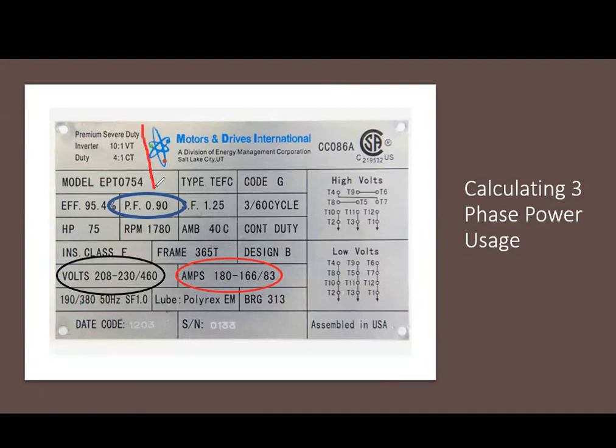And we do have to explain that the power factor is just how we're utilizing that electricity. And so for a motor, what would happen is the voltage sine wave would start first, and then a little bit later, we might have that current sine wave. If they both traveled in unison, or unity, then they would hit their peak at the same times, but they don't because a motor has a coil inside, and it's very difficult for that current to get through that coil. So it lags a little bit, and they put right on the nameplate what the power factor is. So already we're not utilizing all the electricity because of the power factor.